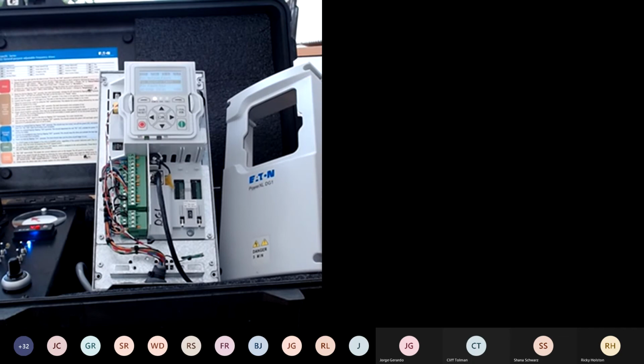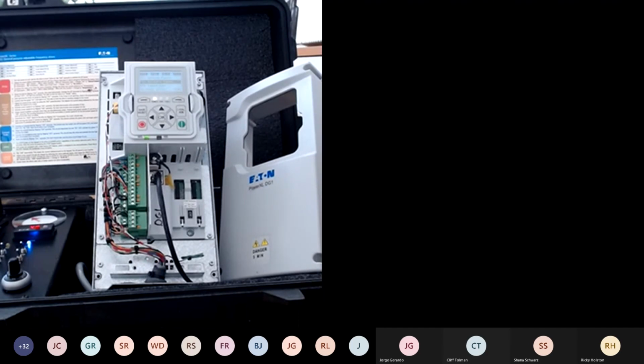I know I default to harmonics because it's one of the most interesting, fascinating things we can see, the drive causing distortions onto a system. Keep in mind that if you have a large facility with large horsepower machines, you may be perfectly fine in your building, but the level of current distortion that you should be mitigating could also spill over onto smaller buildings, or if you have a transformer going down that single line diagram, onto your neighbors.